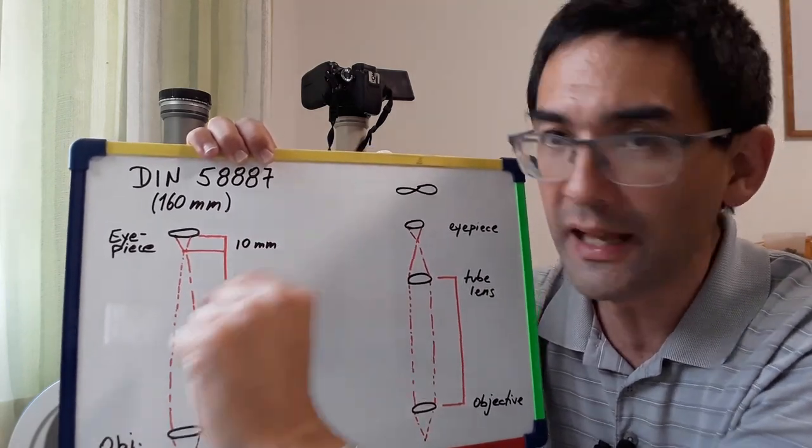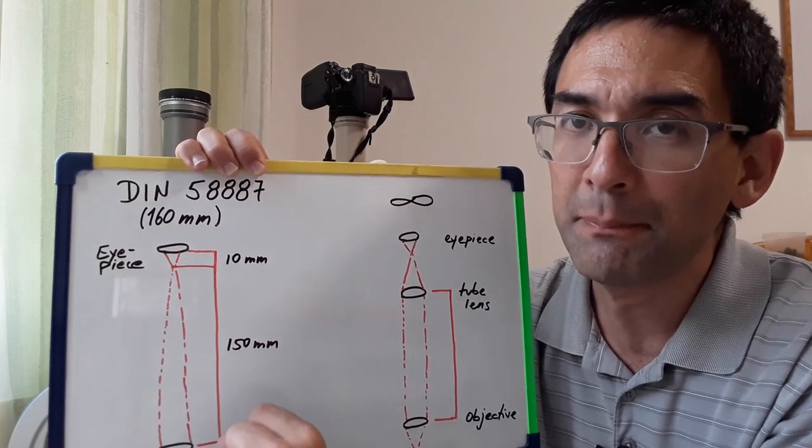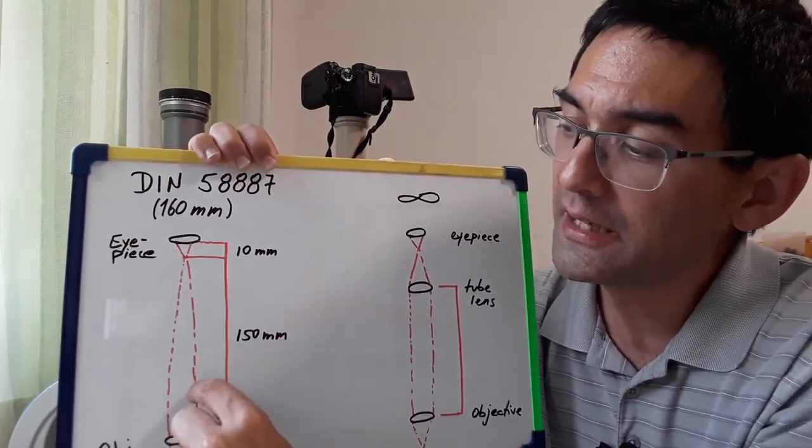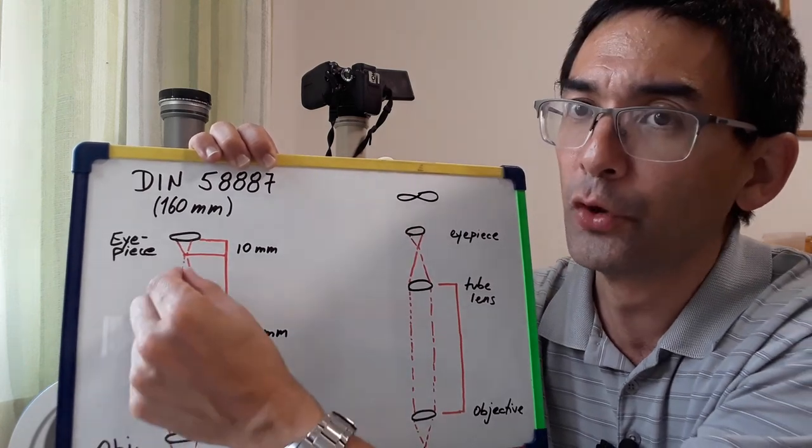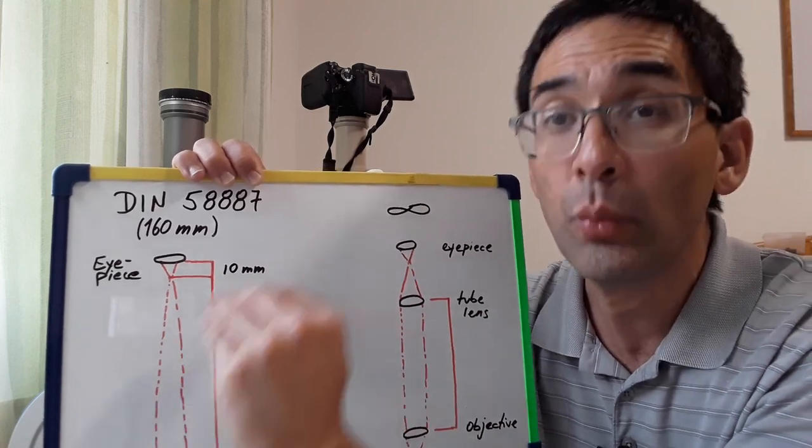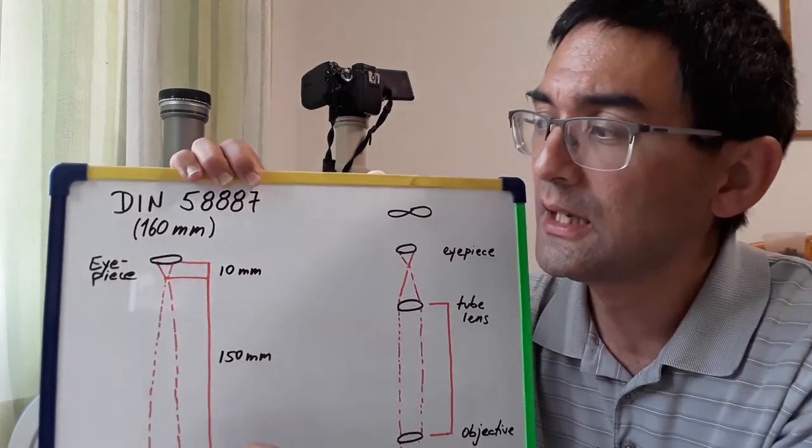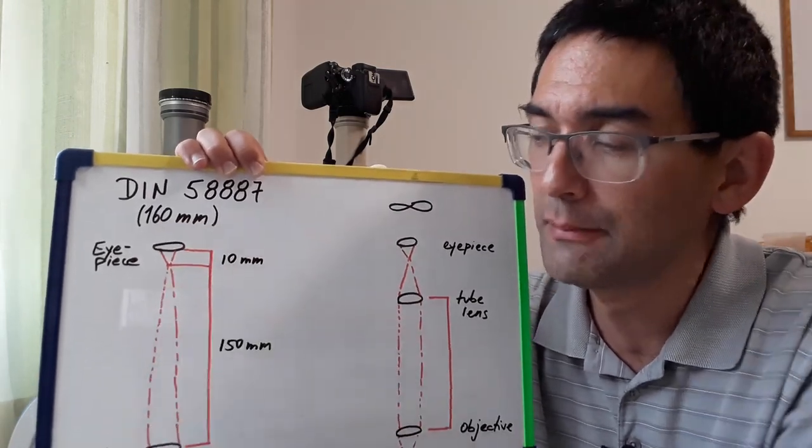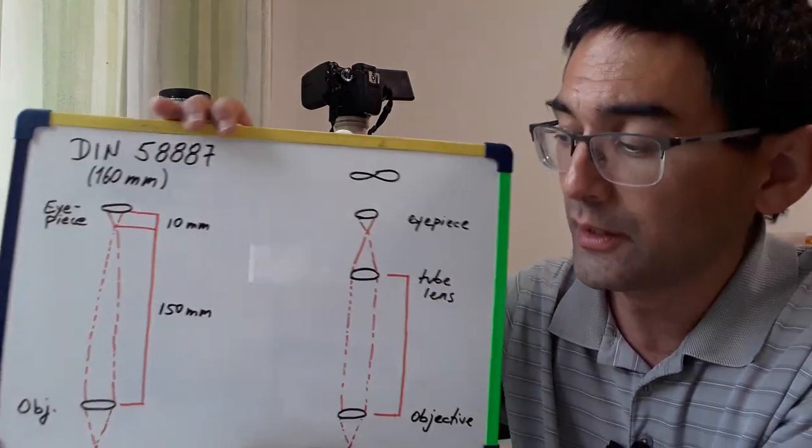But also if you now put a filter in here which is a piece of glass so to say, then what happens is that it also changes the focus a little bit because these light beams here they are not parallel but they converge together. So two disadvantages: you cannot put any filters in there without changing the focus and the second thing is that the size of the microscope is fixed and limited.